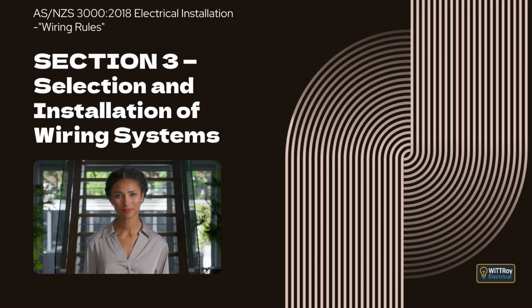Clause 3.7.2.2, Preparation for connection. This clause states that insulation must only be removed as much as necessary to make the connection. Where insulated conductors are joined, the joint must be insulated to a level not inferior to the original conductor insulation, and any damaged insulation must be reinstated.